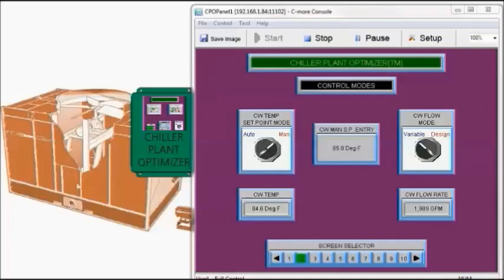Now, I'm making one more change, which I'm going to call state 4. And I'm going to adjust the condenser water temperature set point mode into the auto mode. And then we'll see a change in the condenser water temperature. The condenser water temperature has dropped now from 85 degrees down to about 76.3 degrees Fahrenheit. And actually, the flow rate has dropped about 50 GPM as well.